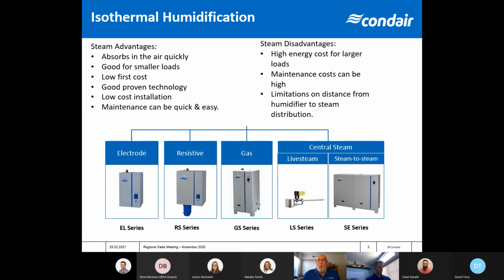So these are great for what I consider to be kind of the medium to fairly large loads. Can save the owner a lot of money in energy that way. And then the ones just to the right here, we have our central steam, we have our direct injection live steam. If a building has a boiler plant, as long as they're providing clean steam, we can inject their steam directly into the duct or the air handler. Or if the boiler is producing kind of a dirty steam, we can use our steam-to-steam heat exchanger. We can turn dirty steam into clean, sterile, atmospheric steam.